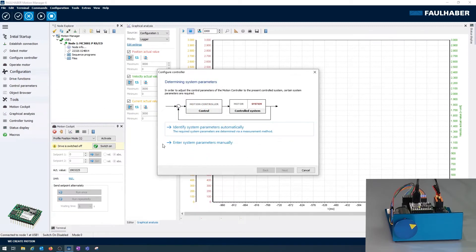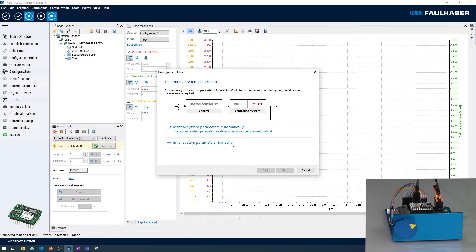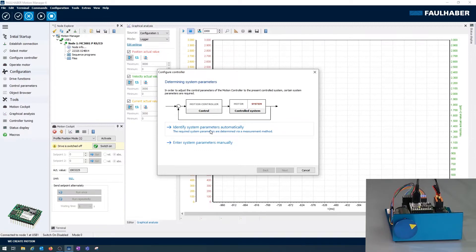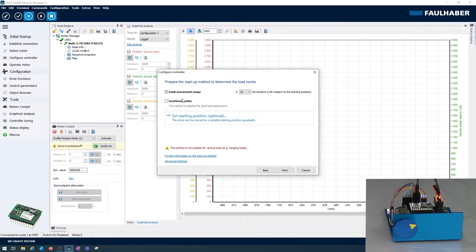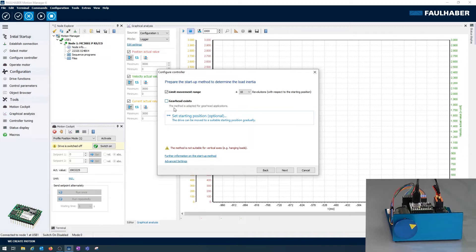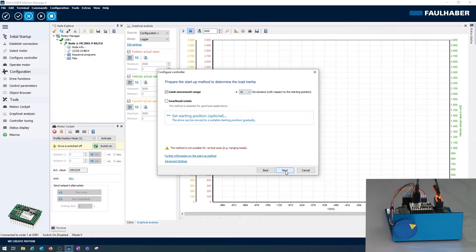It's working in many cases. If it's not possible to be used here then you can enter the inertia parameter manually. In that case shouldn't be a problem. So I can use an auto identification and then there's a page where I could move the motor to the middle of the actual range of movement that is possible or can even limit the range that is going to be used. But I don't have to do this here.